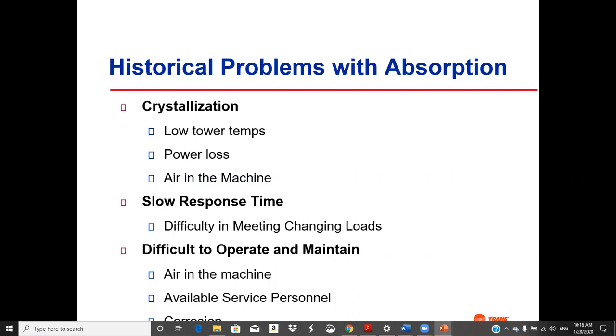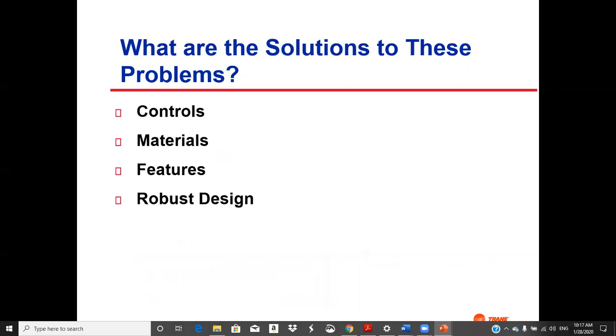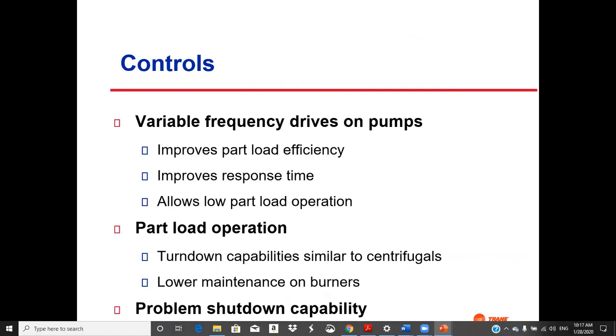But crystallization, we talked about that. We have the high salt concentration, low temperature. This stuff can crystallize, and for these reasons, we went over some of that. Slow response time, that's been a rap on them. And difficult to operate and maintain. Air, because the vacuum is pretty hard. Corrosion, and there may be a shortage of service personnel. Solutions: controls, material features, robust design.